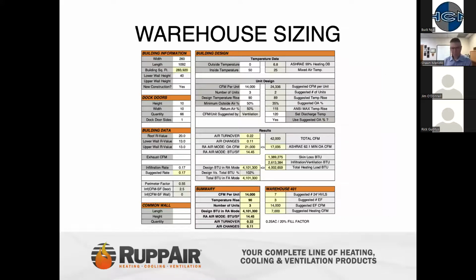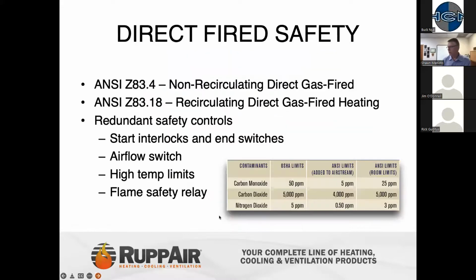Next is: what is the contaminant level from direct fired versus indirect fired? Within the direct fired units, and I'll try to go back to the slide here, it has the emissions. Indirect fired systems are not going to produce any contaminants to the space, whereas direct fired units, because it's an open flame burner producing the emissions, will add emissions into the space. We actually have some additional safety bulletins. I can get into this a little more explicitly, but this is the general production levels. We're typically about 50% of the value you're seeing here, normally about 2 to 2.5 parts per million of carbon monoxide and about 2,000 carbon dioxide. So we're well below those levels that even ANSI tests for.